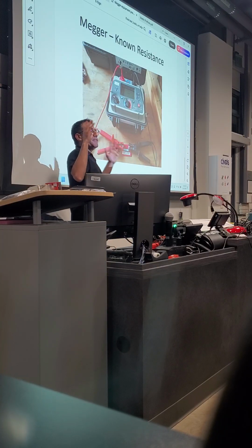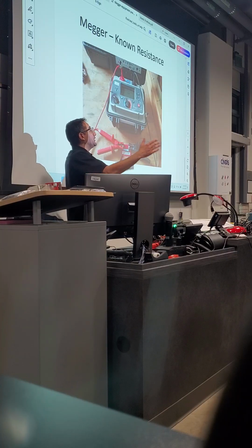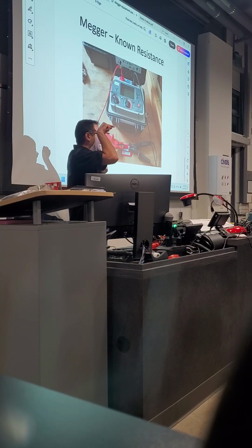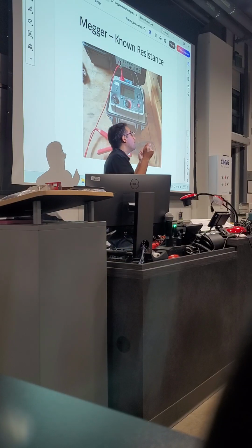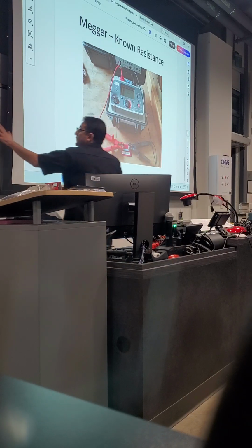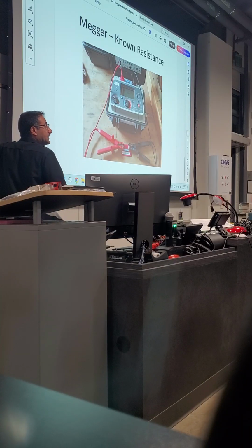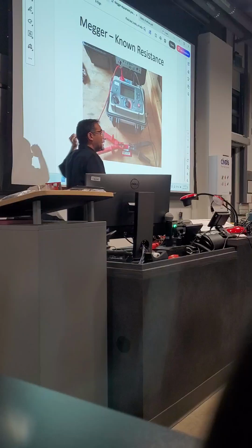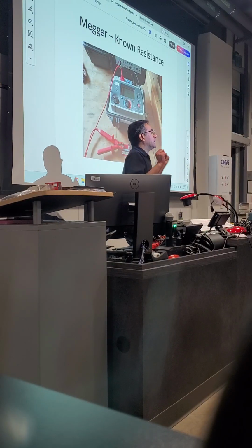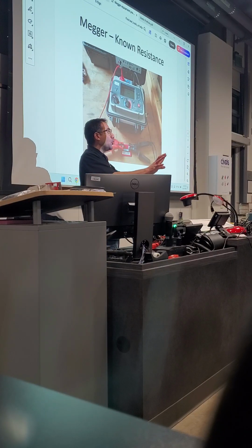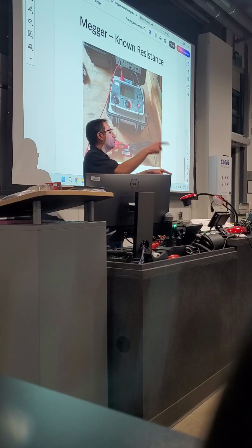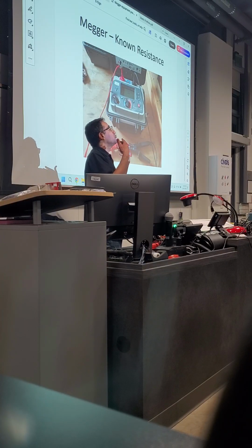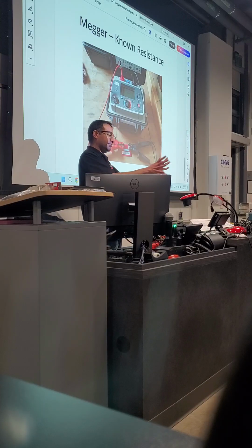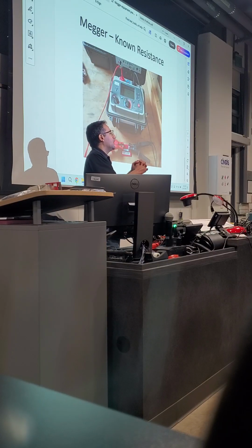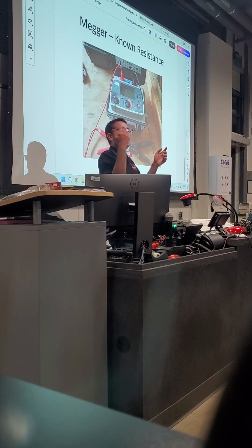Now, before you run the test, let me check your setup. When you start the test, it's gonna push the live voltage, 1000 volt DC. That's a lot of voltage. I've been zapped with that. It's not fun. So when you start the test, make sure you stay clear. Make sure you don't touch the black or red lead. When I say stay clear, just a few inches is fine. You don't have to stay 20 feet away.